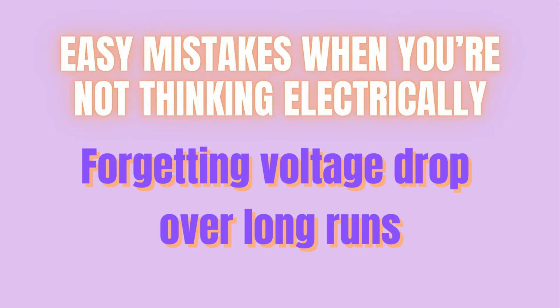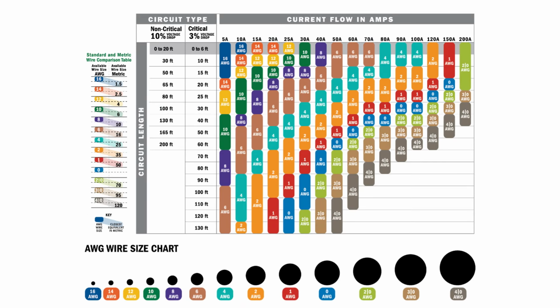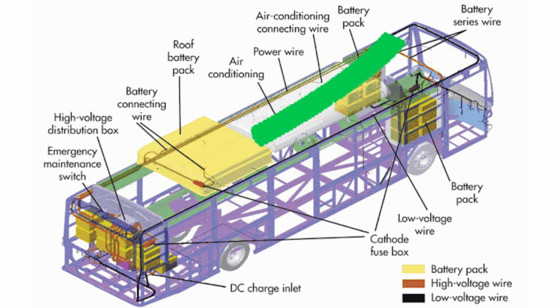Mistake number two is forgetting voltage drop over long runs. Electrical plans include calculations that factor in wire length, because the longer the run, the more likely you are to lose current, since that length creates resistance. Even if your wires seem heavy duty, long distances between components, like a far distance from the inverter to the battery, can add resistance.